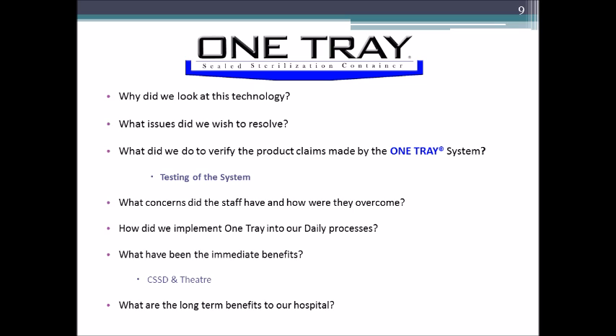We meet all the parameters. We're following the container manufacturer's instructions for use, the instrument manufacturer's instructions for use, and obviously our autoclave's instructions for use, and we no longer have to report that out to infection control. So essentially, 0% immediate use or flash rate, as people like to call it, because of the technology.